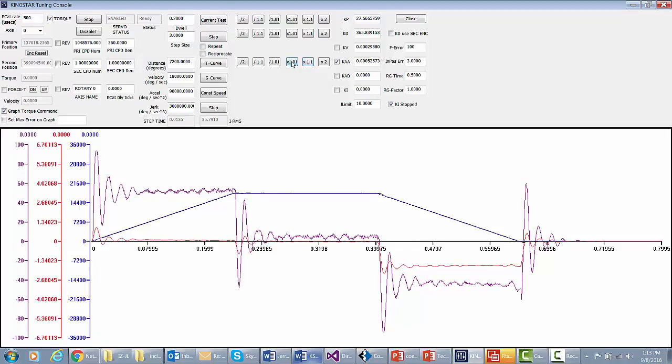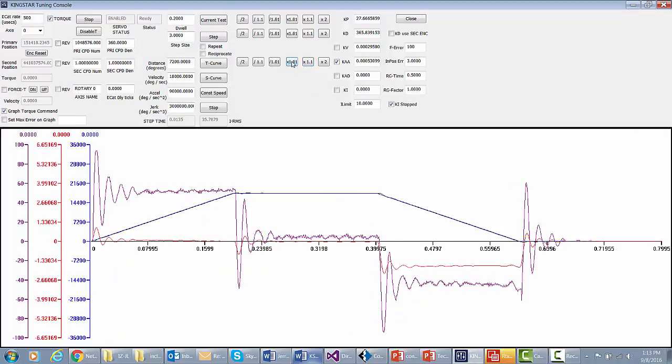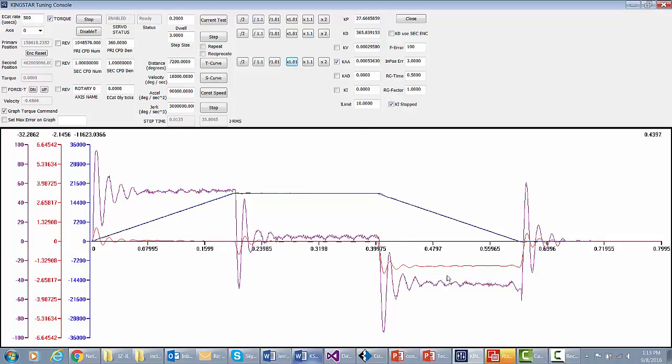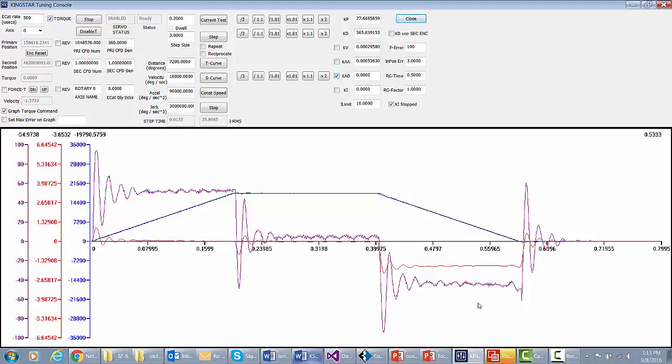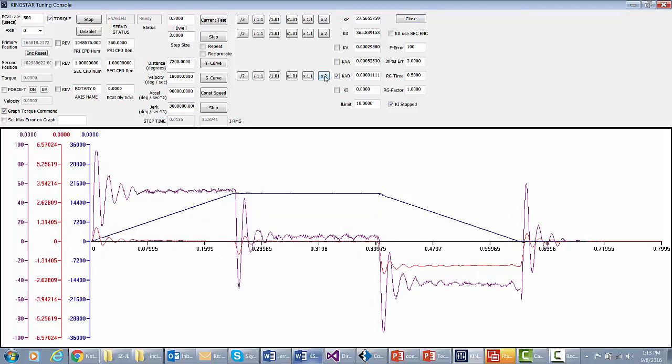Now I'll do 1%. So here we are. This side is pretty good. Notice it had no effect on the deceleration side. That's a separate parameter. The reason we choose to do that is simply that on the way up, on acceleration, friction hurts you, and during deceleration, friction helps you.